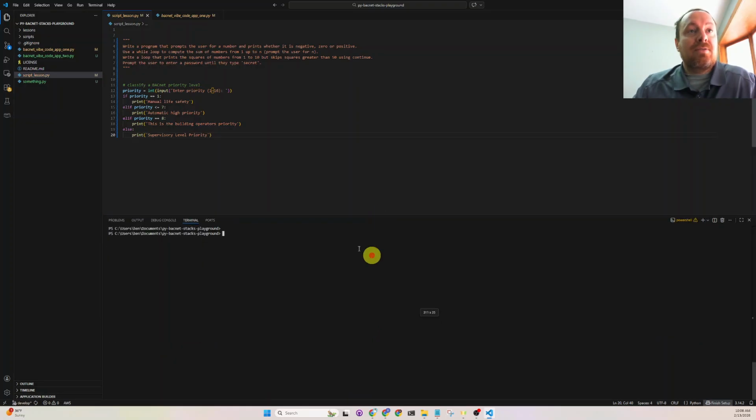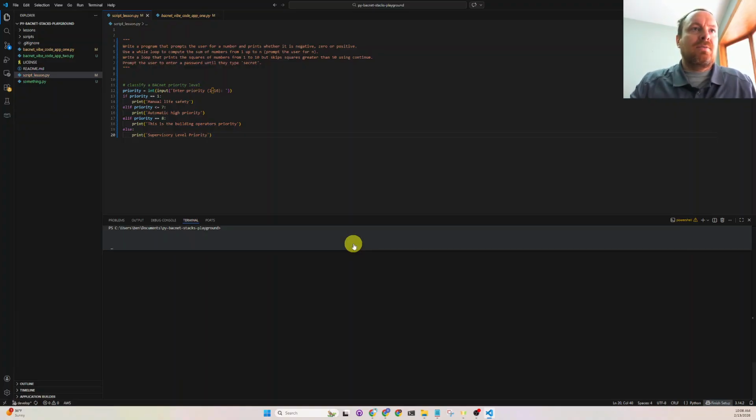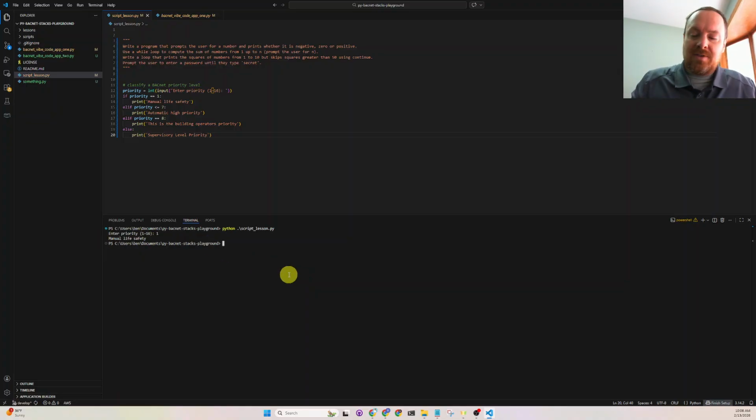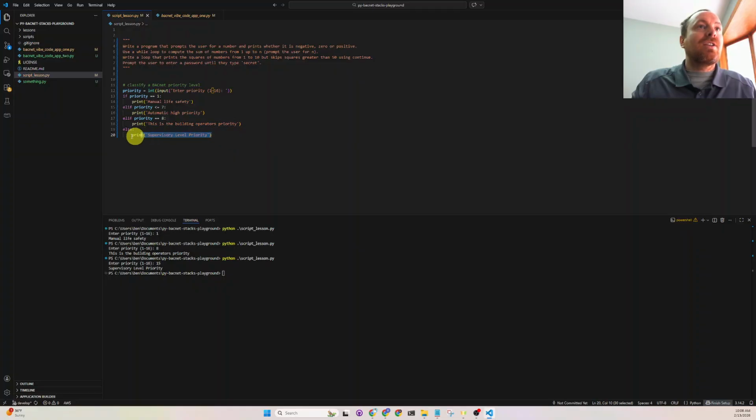And then in our little theory lecture here, we do the Python script lesson. What happened? Something happened. I'm just going to clear that. Type in clear. Python script lesson. Okay, so enter a priority. Comes through as manual life safety. Then if we enter a priority 8, this is the building operator's priority. Pretty simple little program. Priority 15, this is supervisory level priority. So it's using this control structure here, the if elif else.